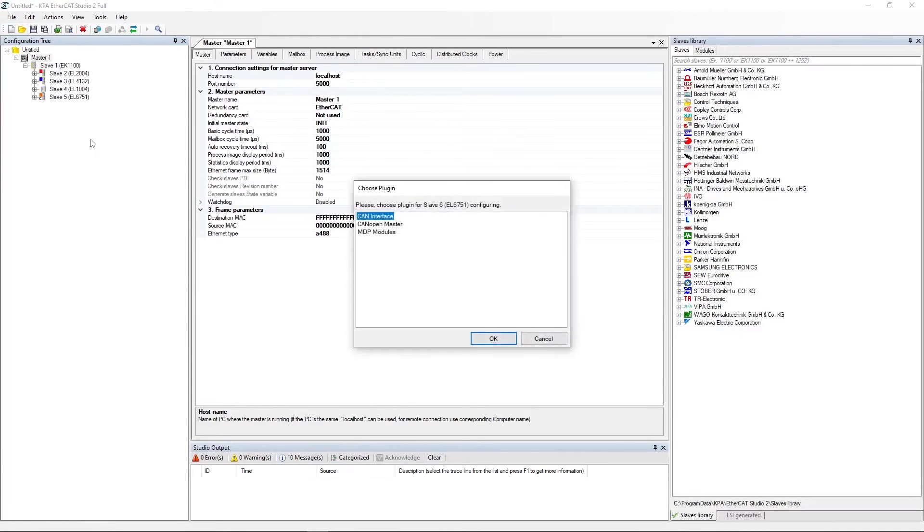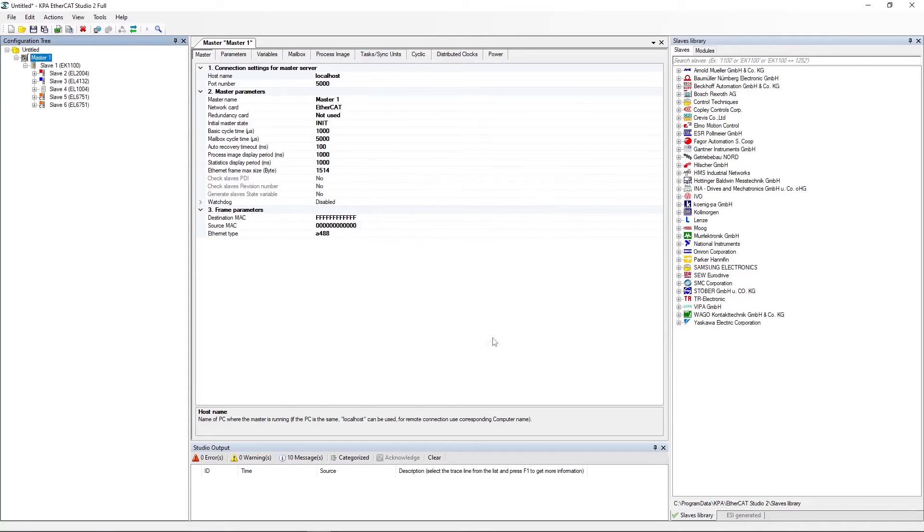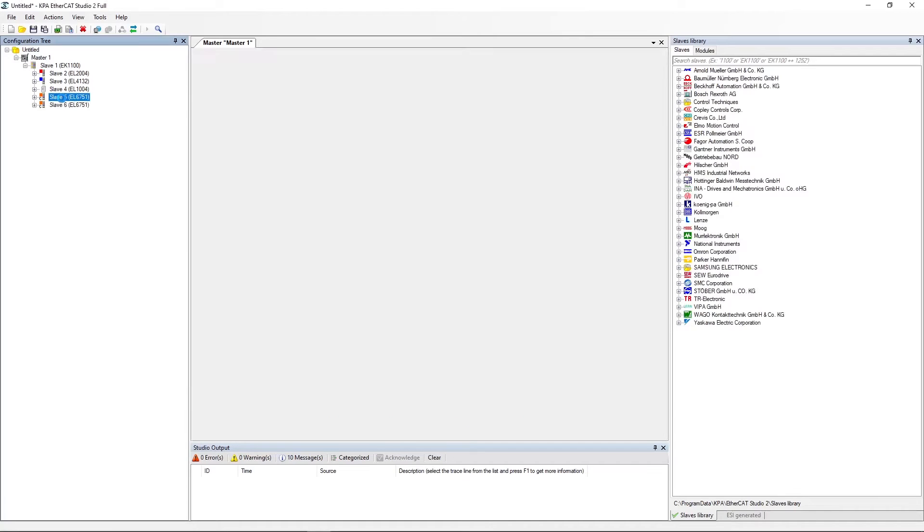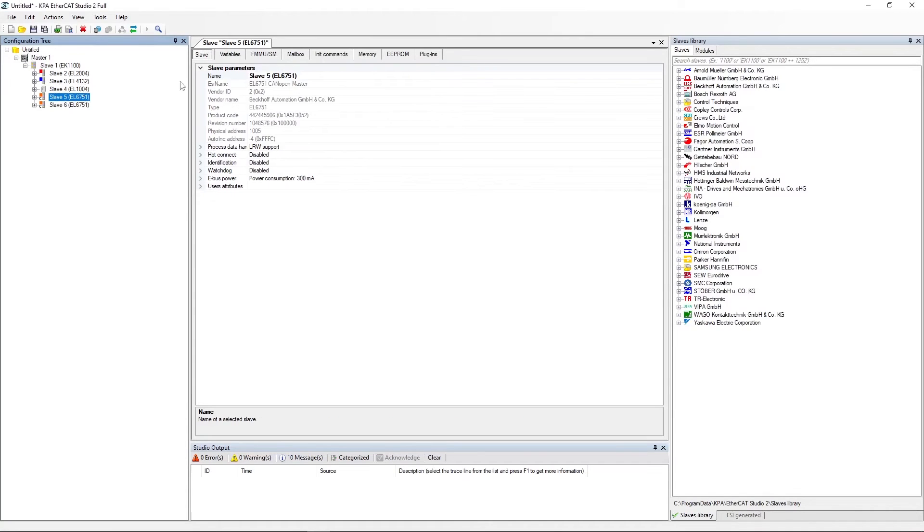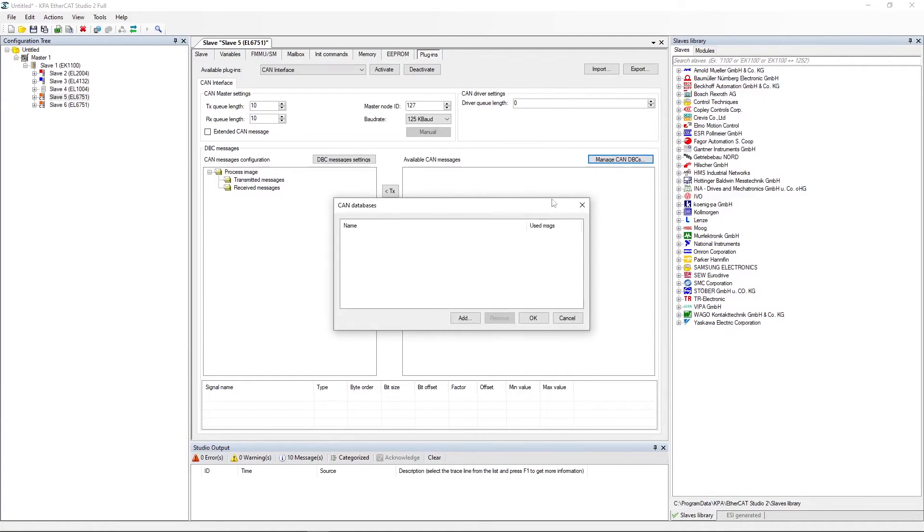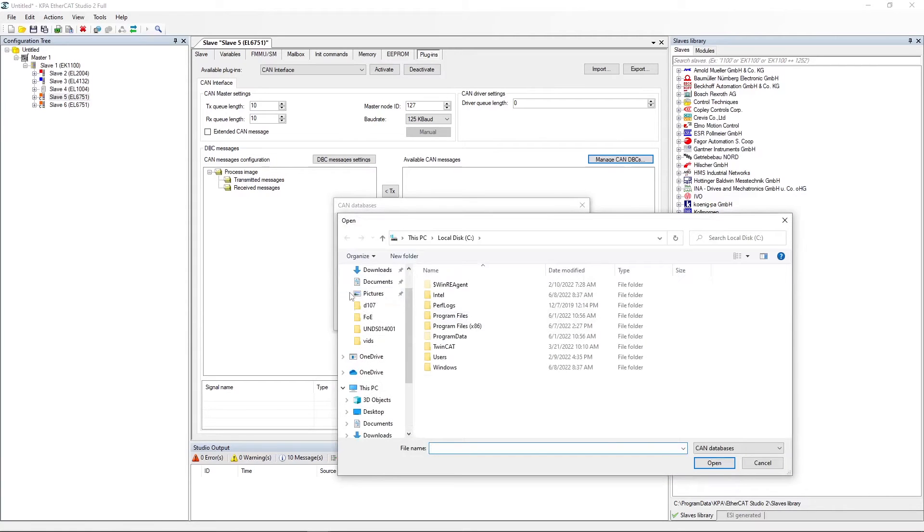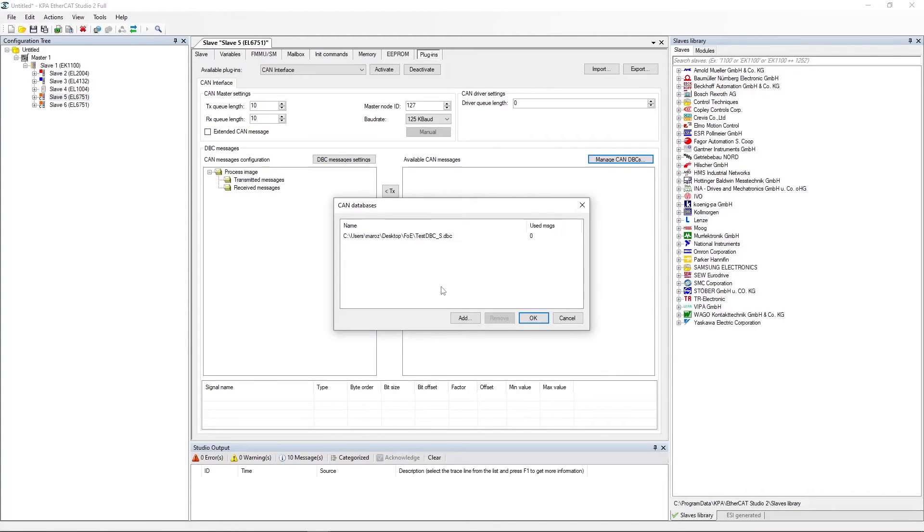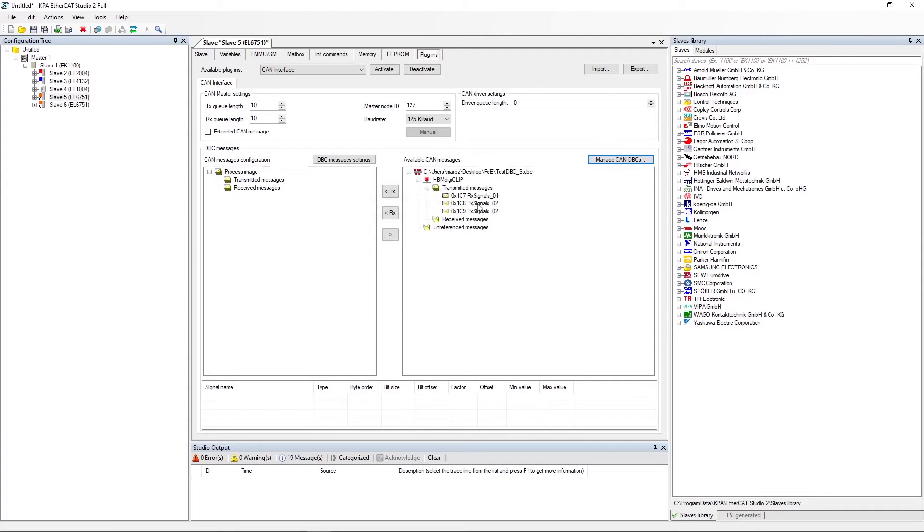In the choose plugin dialog, select the CAN interface plugin. Select the EL6751 slave, open the Plugins tab. Click the manage CAN DBCs button. In the CAN database dialog, click Add and select the corresponding DBC file. Click OK. Move the following message to TX.